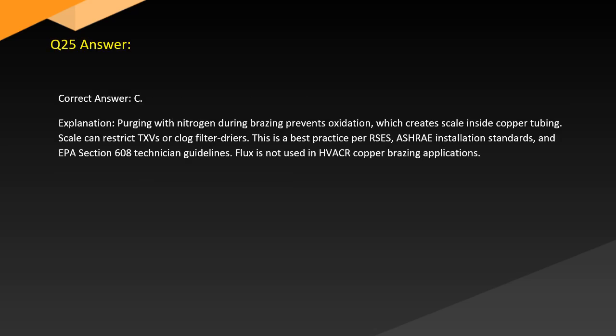Answer. Correct answer C. Explanation. Purging with nitrogen during brazing prevents oxidation, which creates scale inside copper tubing. Scale can restrict the TXV or clog filter dryers. This is a best practice process under ASHRAE installation standards and EPA Section 608 technician guidelines. Flux is not used in HVACR copper brazing applications.